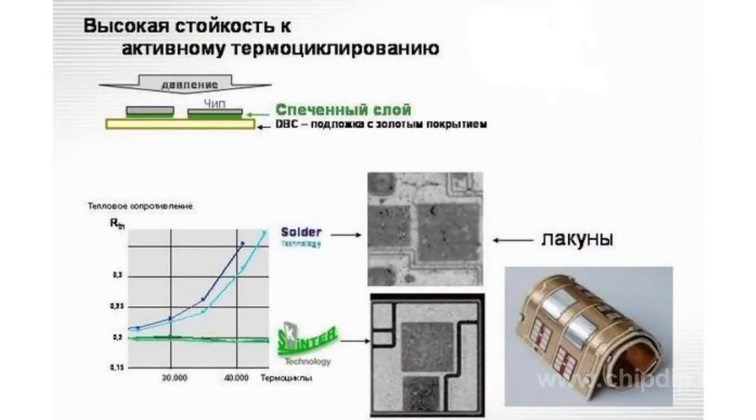In the vast majority of cases, the failure of modules is associated with the soldered joint between the silicon chips and the board. Silicon agrees with the ceramics a lot better than copper. Experience shows that it is the detachment of chips from the insulating substrate that is often the key reason for failure of power modules.